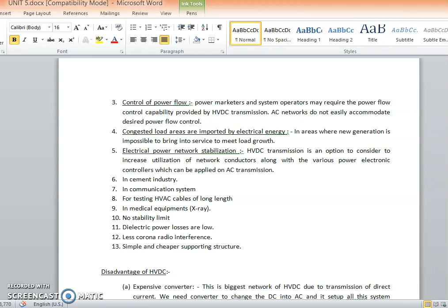And what are the disadvantages of HVDC? Obviously it requires converters. Expensive converters on both sides are required. This is the biggest drawback of HVDC. Due to transmission of direct current, we need converters to change the AC into DC and back, and transformers to step up the voltage. Another thing required is reactive filters. After passing through the converter, many types of harmonics occur, and to remove these harmonics filters are required. Due to this, transmission cost increases.